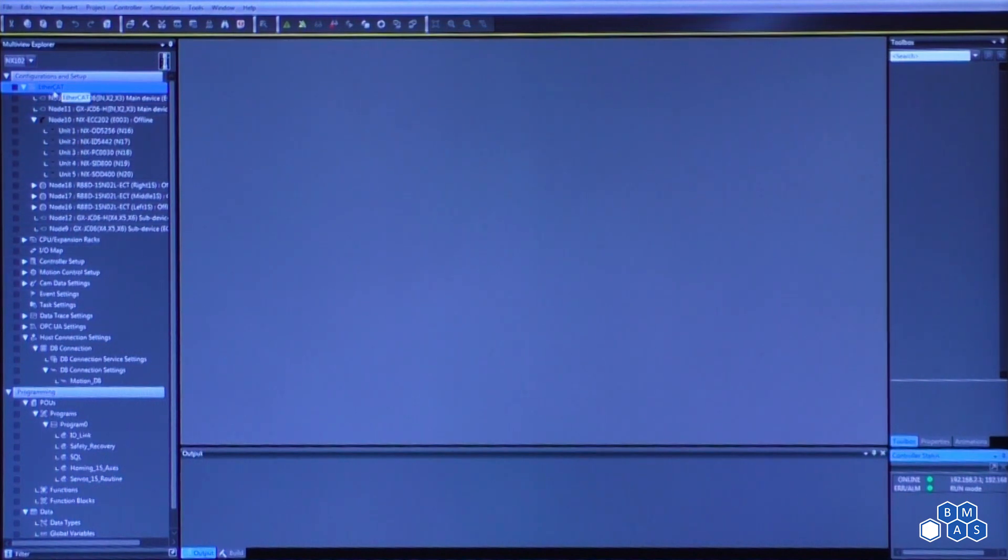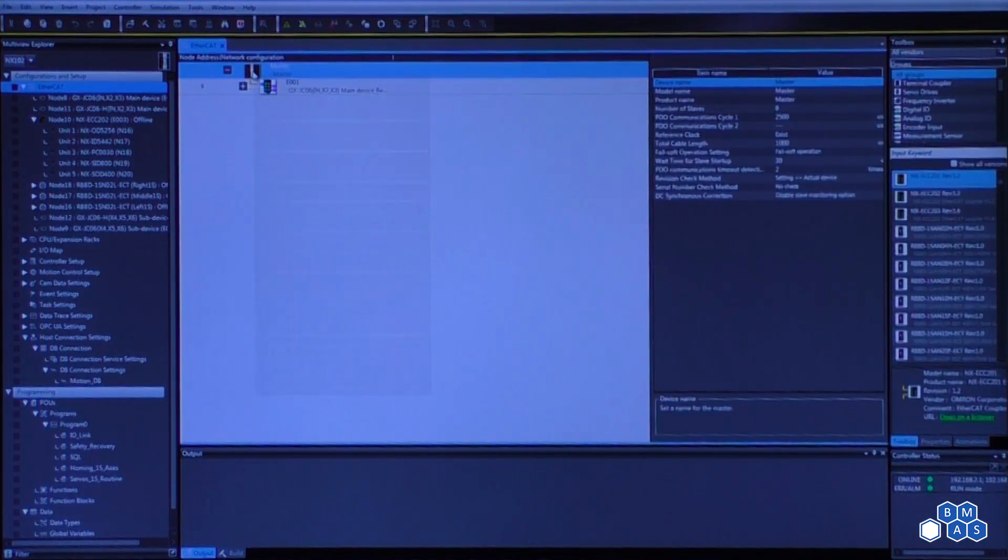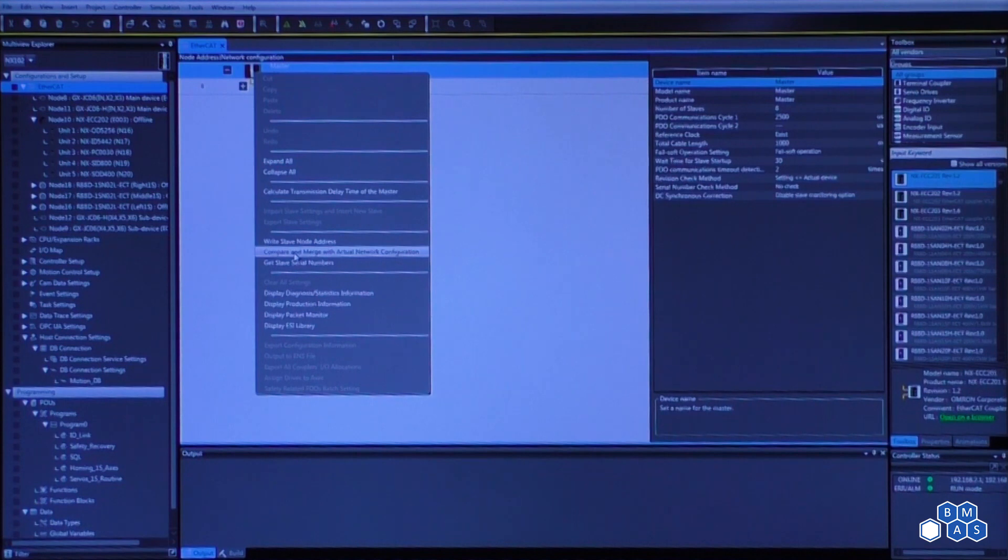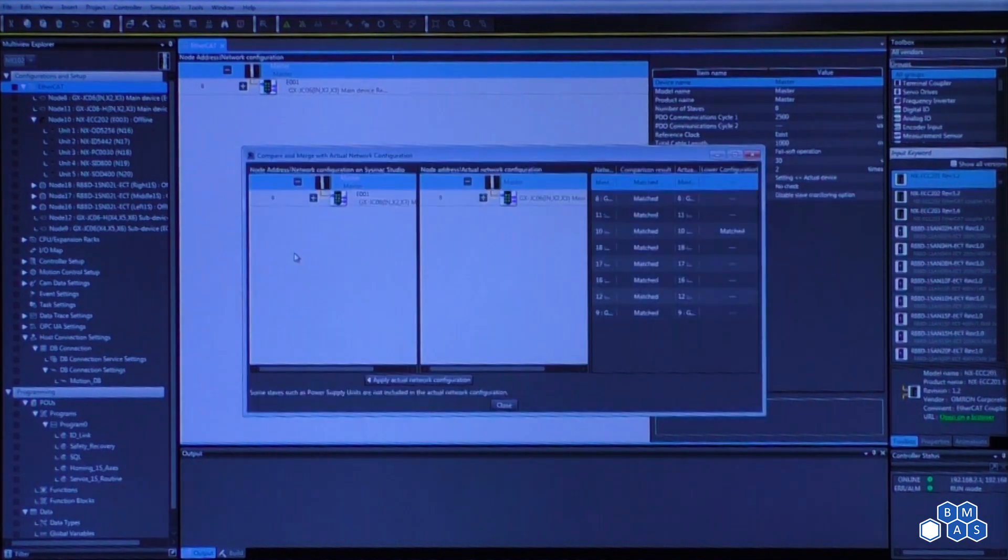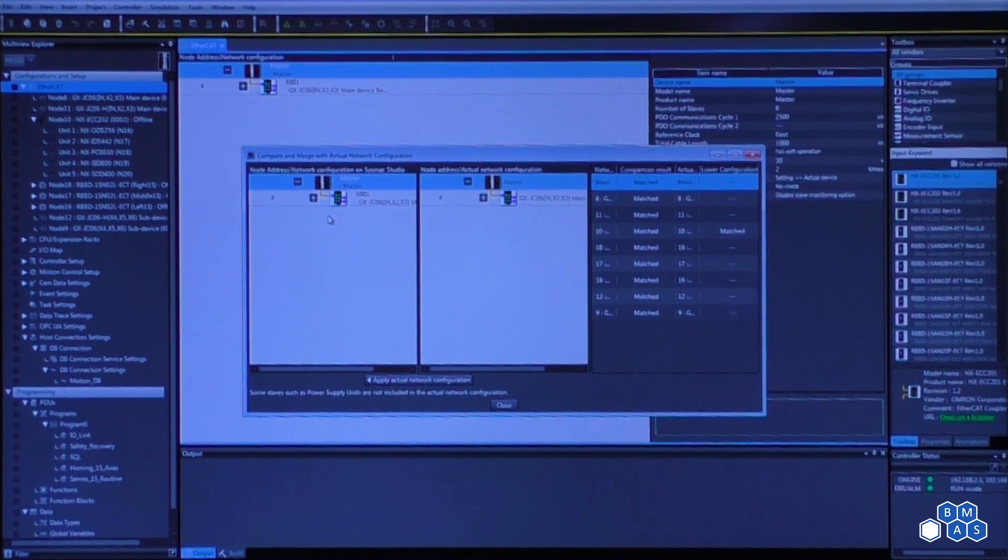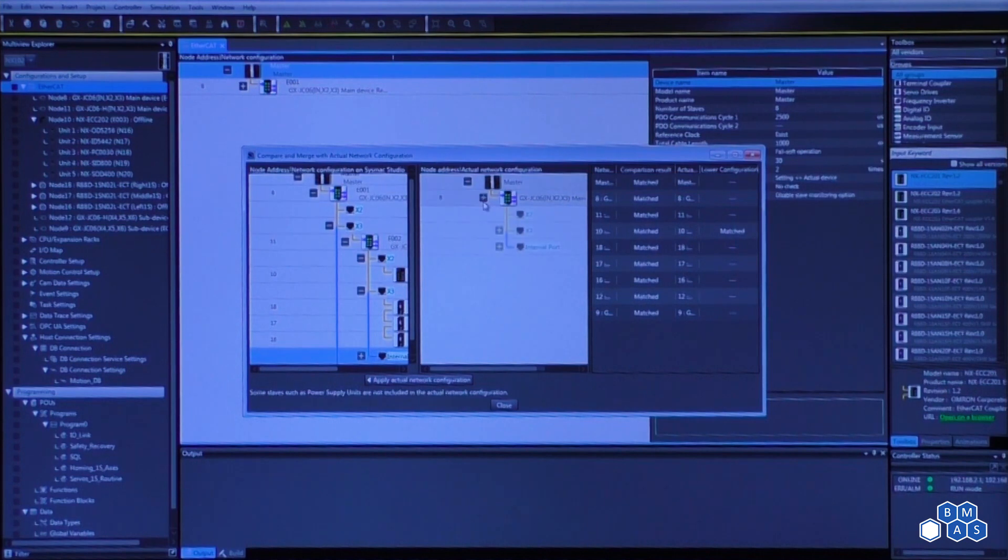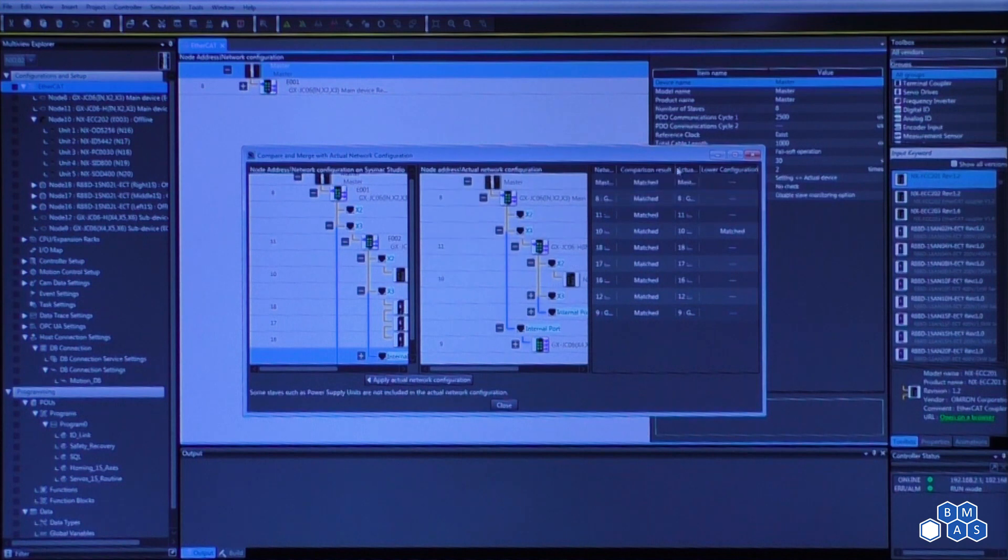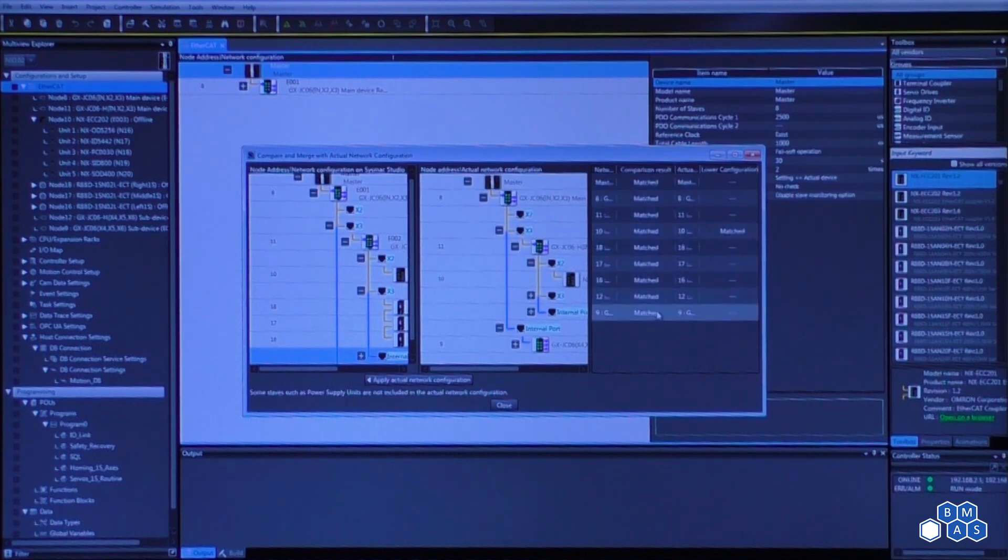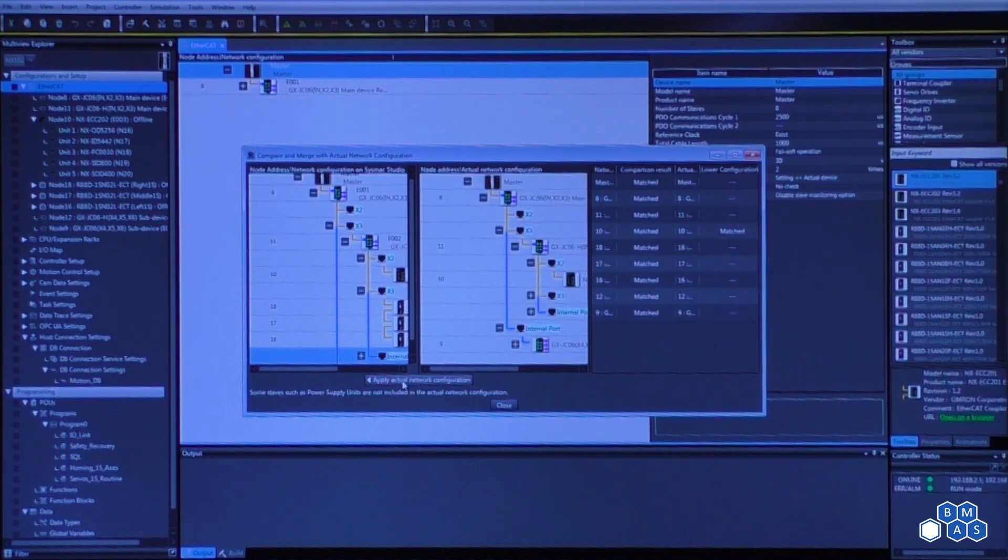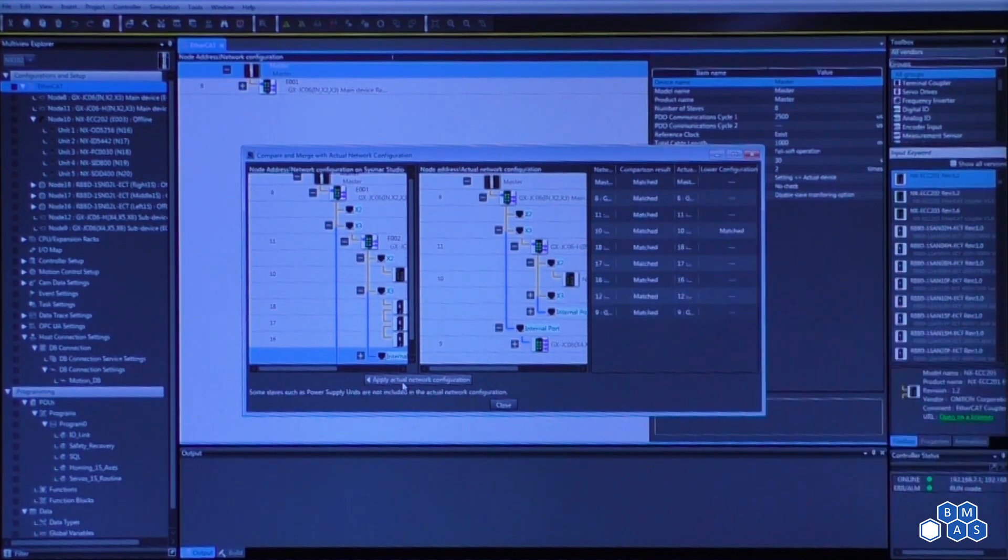The first thing that you see listed at the top is called EtherCAT. What we'll simply do is go in while we're connected to the processor. What we're going to do is click on what's called compare and merge with the actual network configuration. What this is doing is it's going out and it's searching for what is physically connected on EtherCAT and it's going to report it back. If we expand what is in the project versus what is really out there and we take a look at what we see in the comparison result on the right, everything matches. If they did not match or if this is a new configuration, all we would have to do is say apply actual network configuration. Everything that you see on the right would be applied to the left.